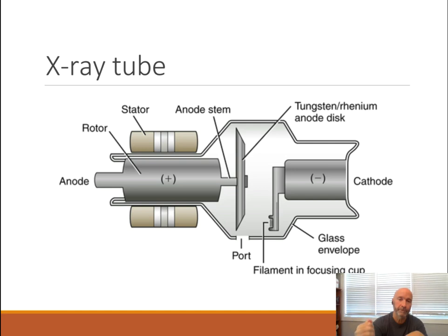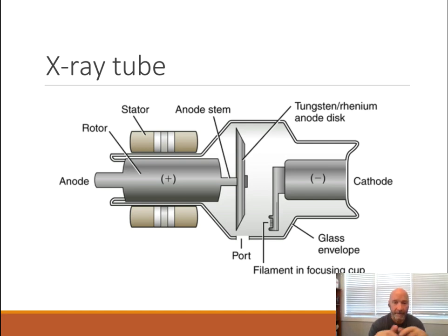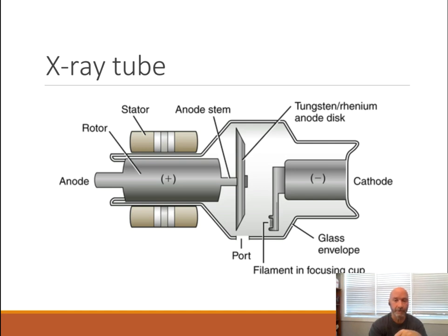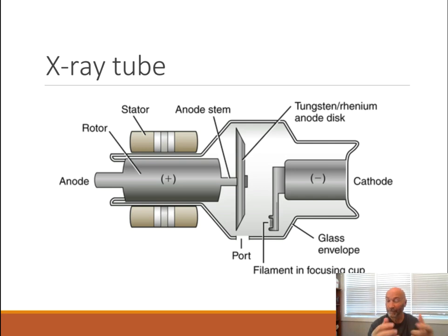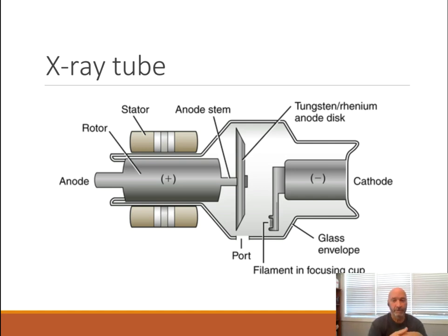It's not until you push the exposure button that the electrons travel from cathode to anode. The cathode is the filament. We take all those hot electrons — what we refer to as thermionic emissions — and send them across the x-ray tube to interact on the face of the target on the anode. What happens is it deposits a lot of heat, creates a few x-rays, and creates some light. What we're after is the x-rays. Unfortunately, about 1% of the electrons sent across the x-ray tube become x-rays — the rest just become heat and light.